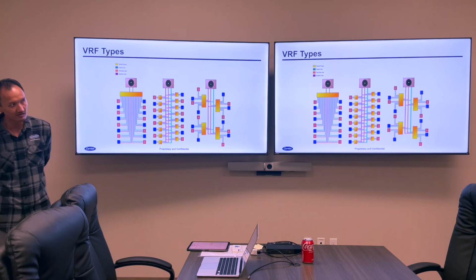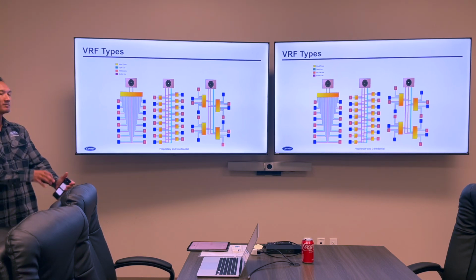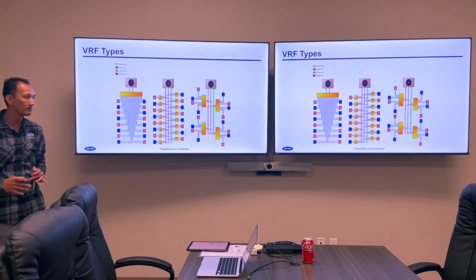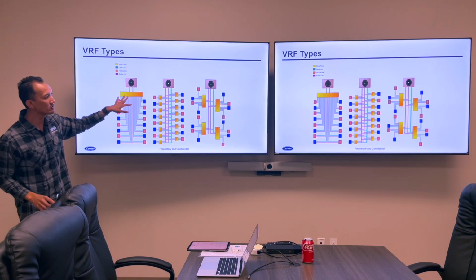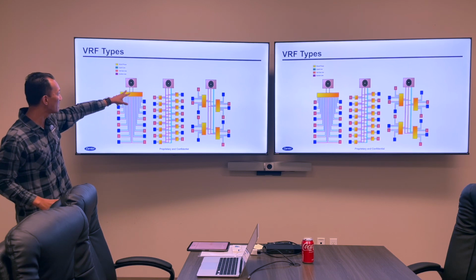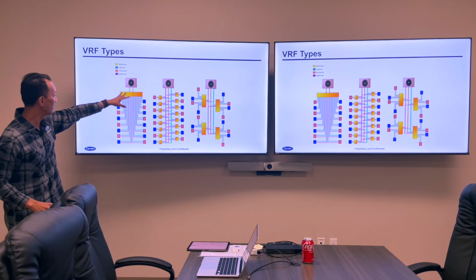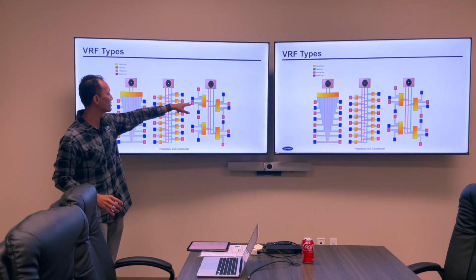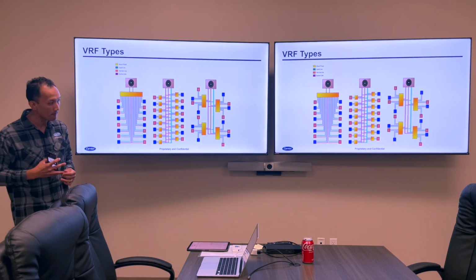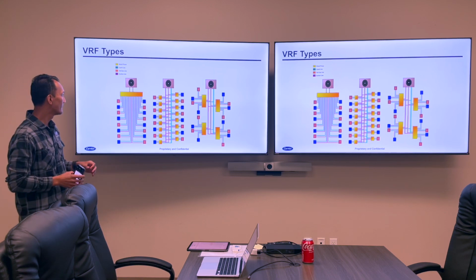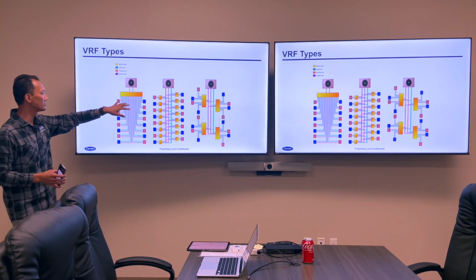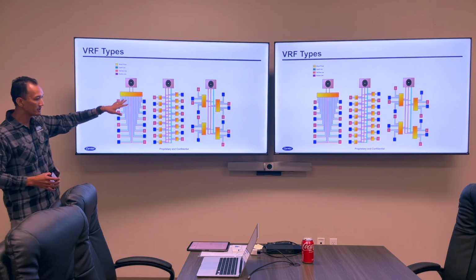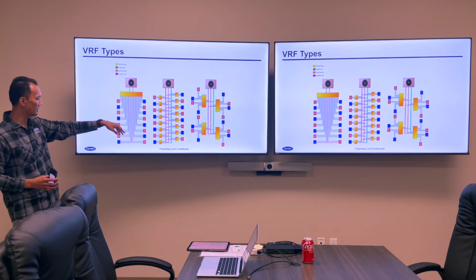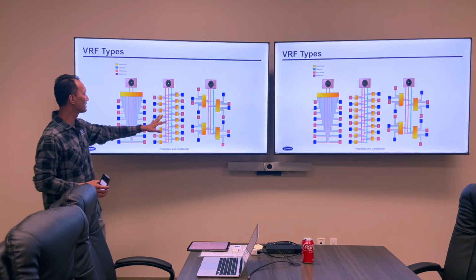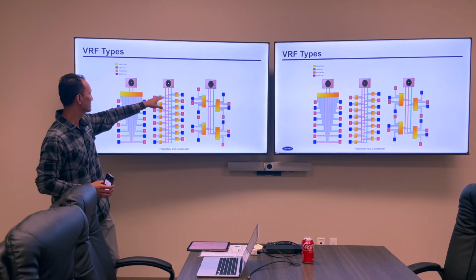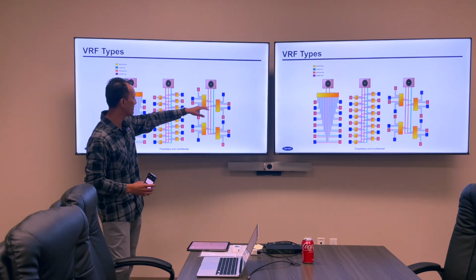I like to show this slide just to show kind of schematically the differences between two-pipe and three-pipe heat recovery. So on the left, we have a two-pipe system. You can tell because there are two pipes going from your outdoor unit into the MDC box, and then the two other examples on the right are three-pipe heat recovery systems. On the left, two-pipe system, you've got one big MDC box, and then you've got refrigerant lines going all the way to your different fan coils. On a three-pipe system, same idea, three refrigerant lines coming from the outdoor unit.